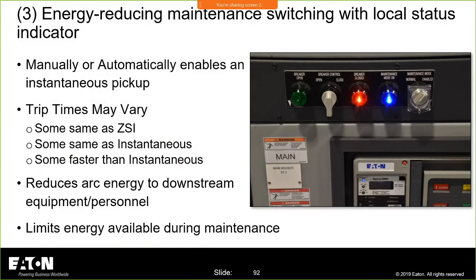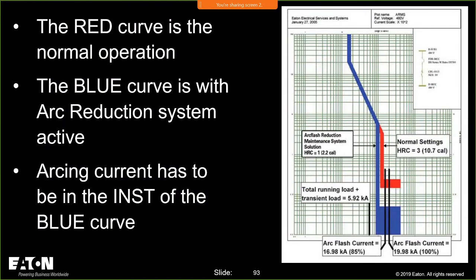Now, here's what I like. My suggestion to everybody, I know we have some buttons on our breakers, is to create a little panel like this. And you know what I love about this button right here? You can open that door, you can close that door, and you can put a lock on it. And locks are good for lockout tagouts. Now, I know you can put a lock on some of our face plates and things of that nature, but this is really nice. You got a nice big blue light. It really shows you when it's on and when it's off. It's there for when we're in maintenance mode. The electrical worker will love you for it. This is basically what it does.